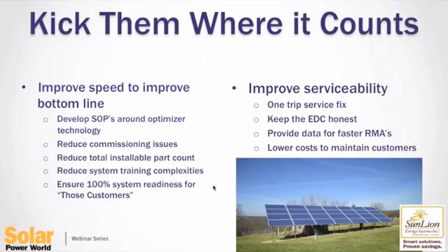And we're only able to do that with a very, very high level of granularity to the monitoring. We keep the EDCs honest. I can't tell you how fun it is to tell a power company that they have a problem with a system, and I've got data to prove it. That's always a fun conversation. But we have found a lot of power problems that have gone on for years that were affecting the customer even before the PV was installed.